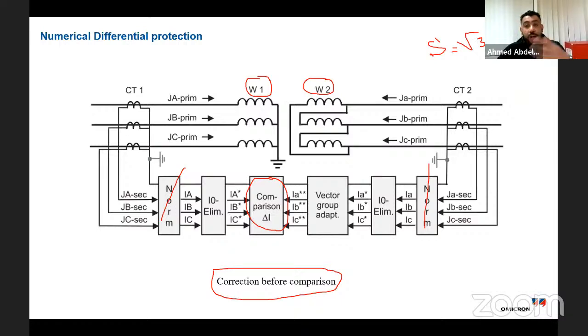So regardless of the value of the voltage, regardless of the value of the current based on the turns ratio, at the end the value in megavolt ampere or kilovolt ampere is the same. So I need to bring all of them to the same apparent power, which is the reference value. So I need to do normalization. I need to normalize the current secondary and the current secondary, here I_A capital, which is the primary side, and I_A secondary, which is from the low voltage side. So I need to normalize.